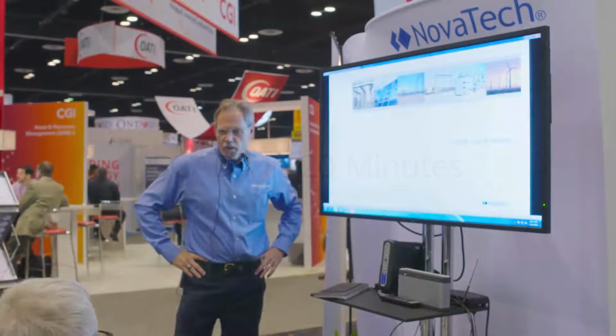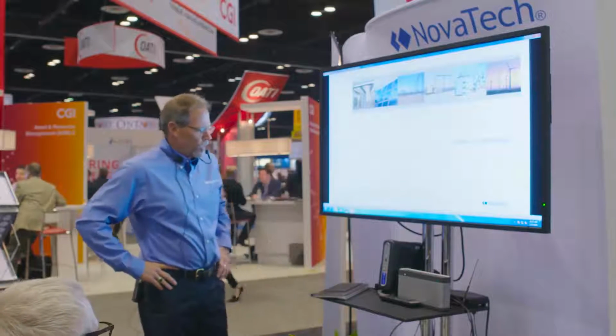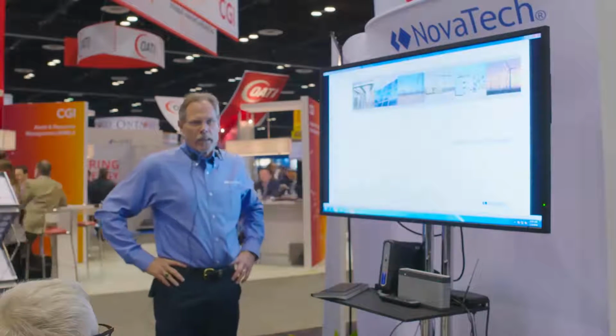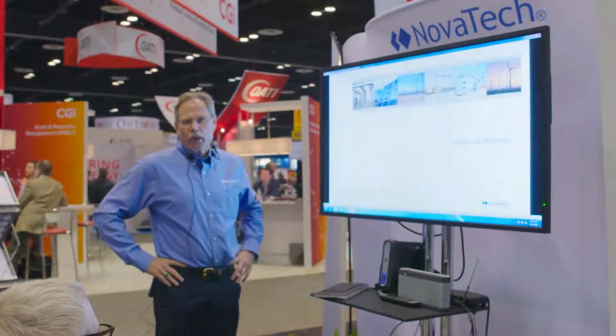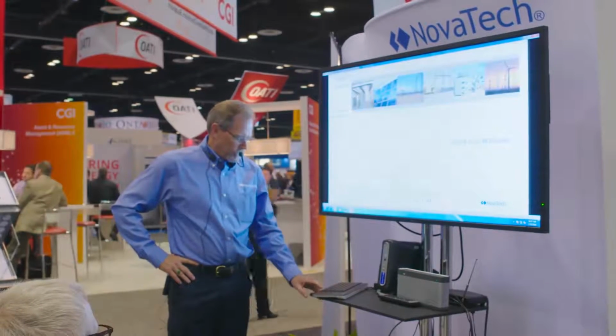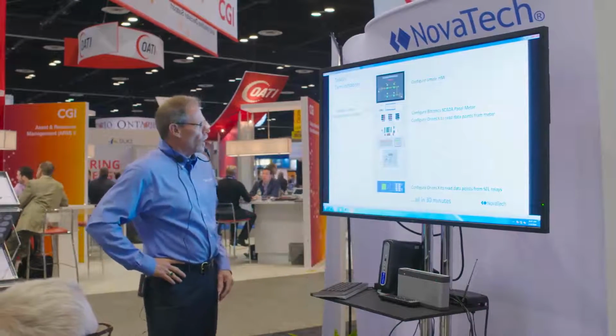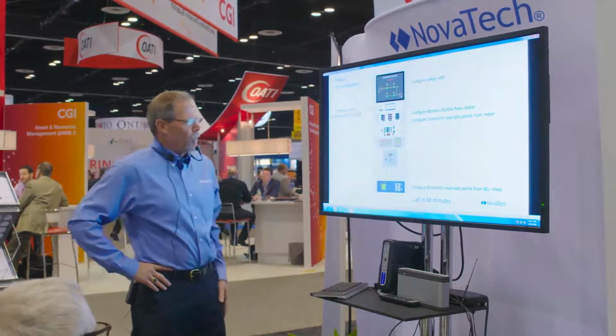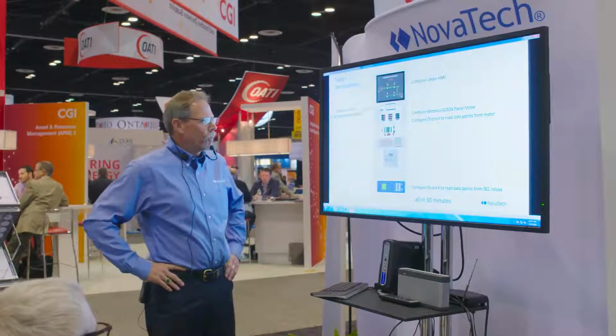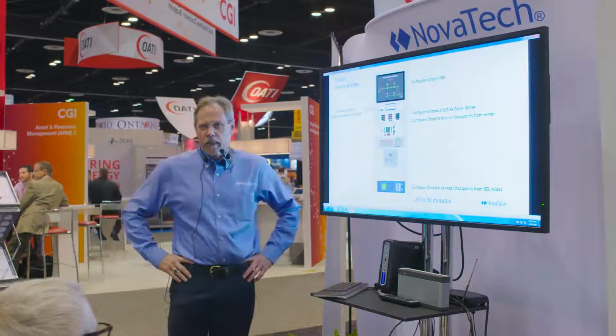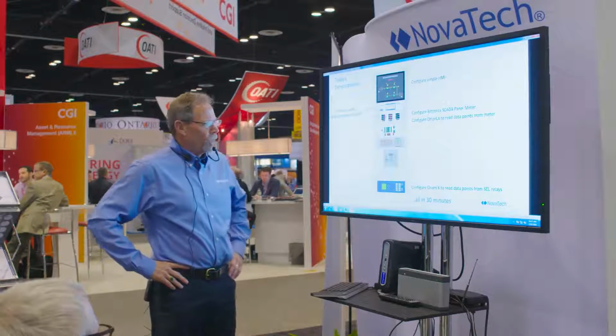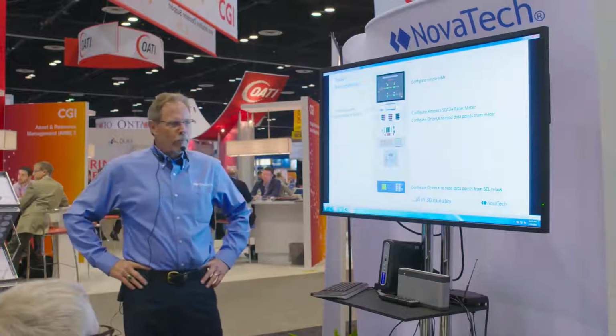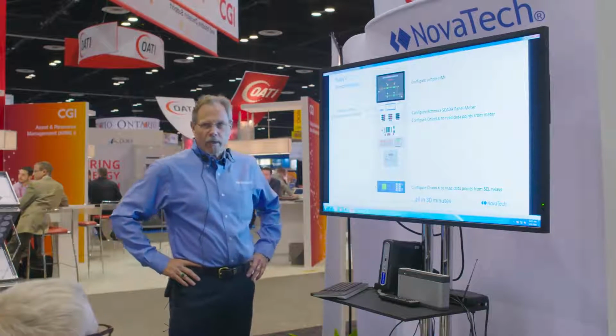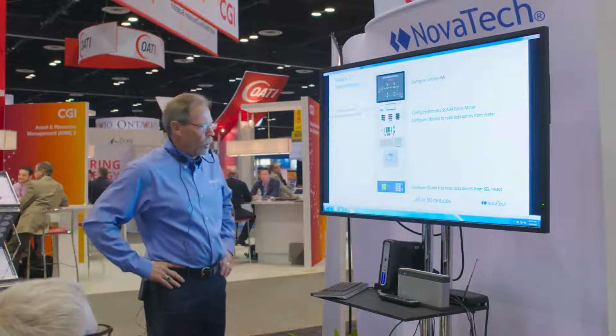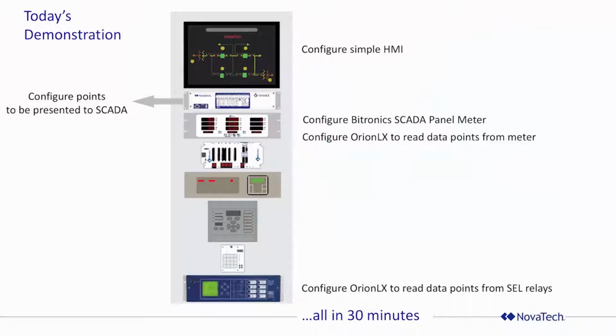What this presentation is going to entail is how to set up a SCADA system in 20 to 30 minutes. First thing we're going to do is we're going to configure a simple HMI. We're going to configure points from a Bitronics SCADA panel meter. We're going to configure the Orion to read the points from the meter. We're also going to configure the Orion to pull points from Schweitzer relays.